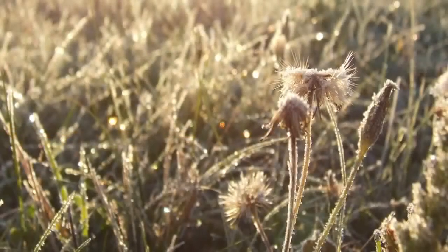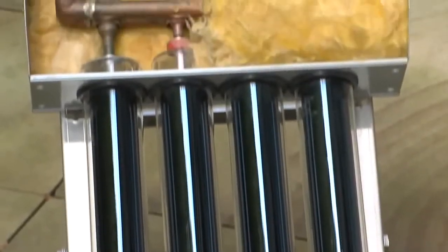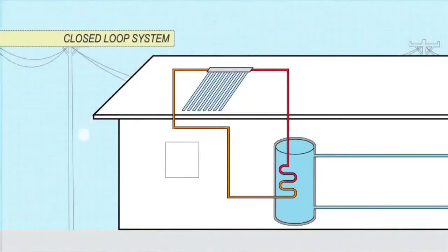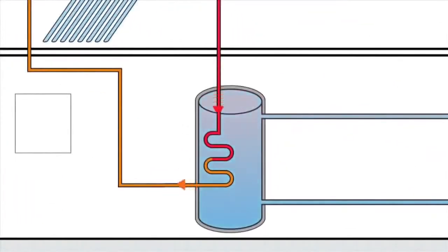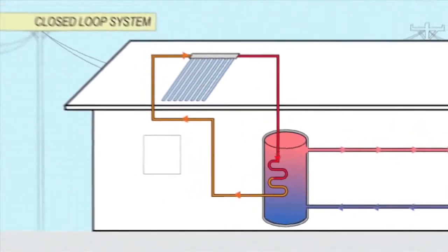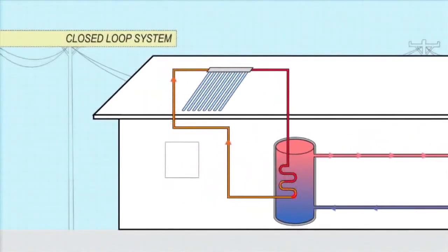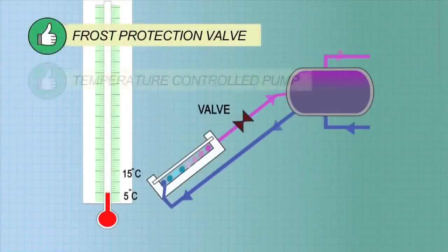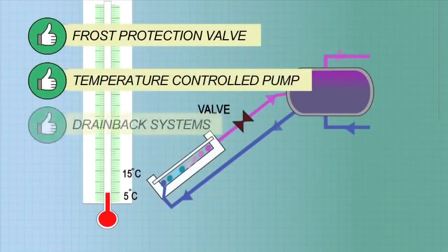In places with minor frosts, evacuated tubes may offer enough in-built protection. In climates with regular frosts, indirect or closed-loop systems are the most popular and reliable form of frost protection. Instead of water, an antifreeze fluid is heated in the collectors. The antifreeze passes heat onto the water via a heat exchanger. The antifreeze does not come into contact with the household water supply. Other frost protection methods are available, such as frost protection valves, temperature programmable pumps, and drain back systems.